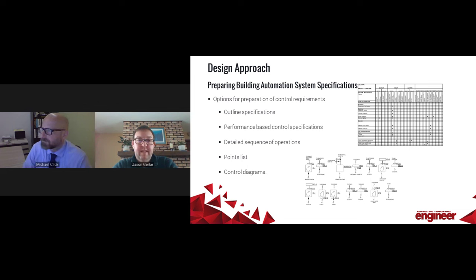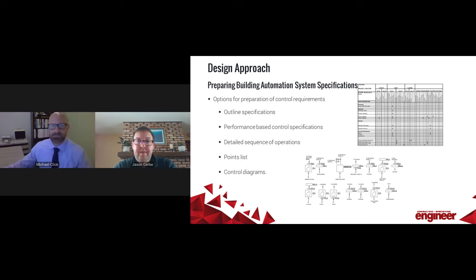Another step up from the outline format is to prepare performance-based specifications for the building automation system. These specifications might be on a plan sheet but are more commonly in a specification booklet. This specification format for controls will describe the sequence of operations, reference equipment types, and define the required outcomes. The next level above performance-based is a detailed sequence of operations — more sophisticated, identifying specific equipment designations and labeling of control devices, describing what is happening when.